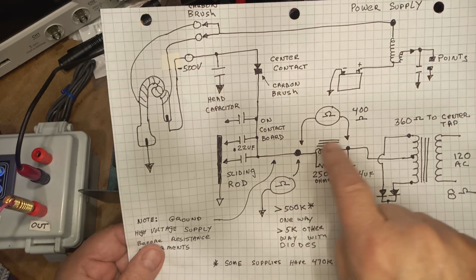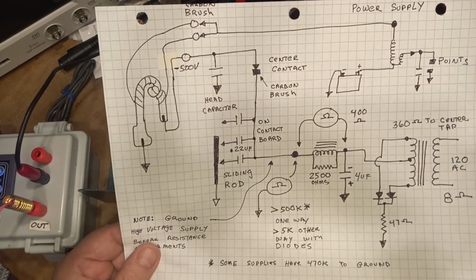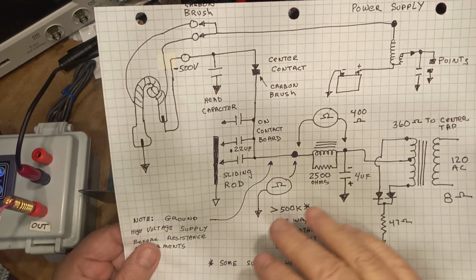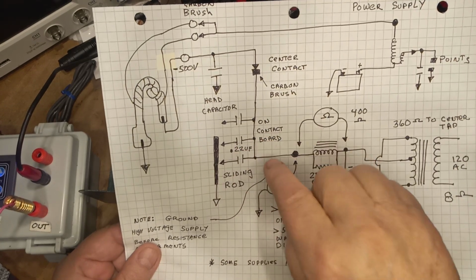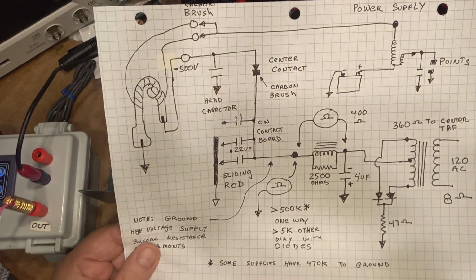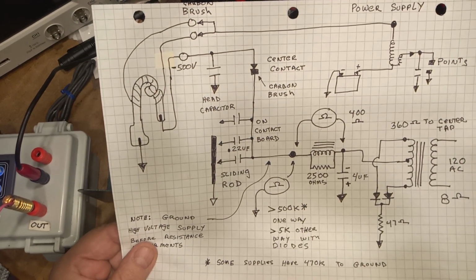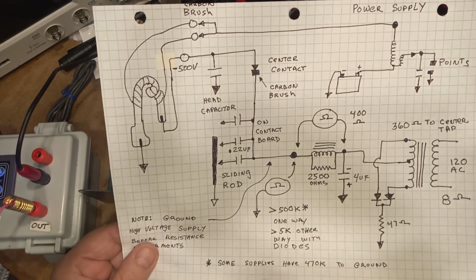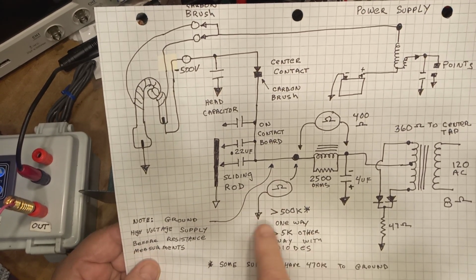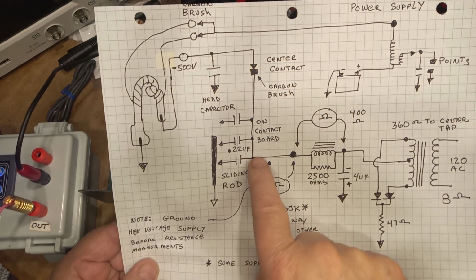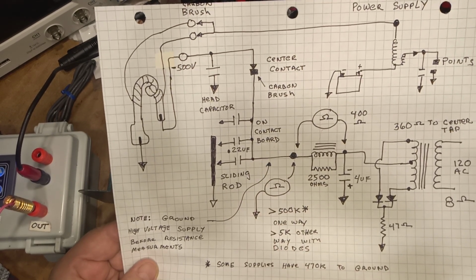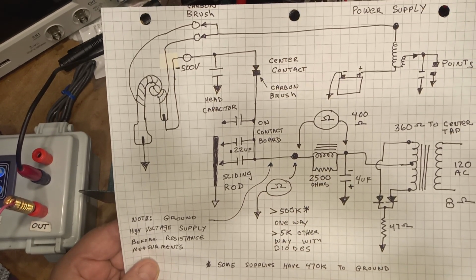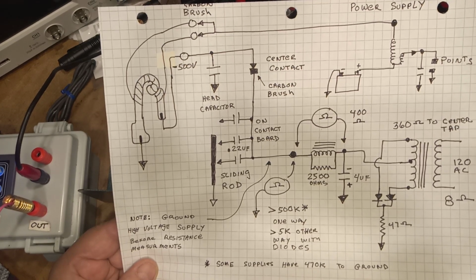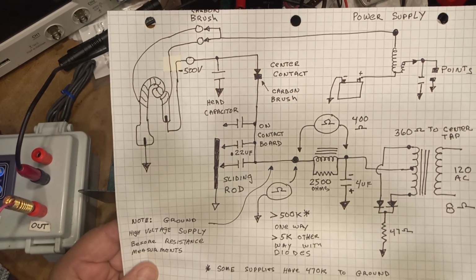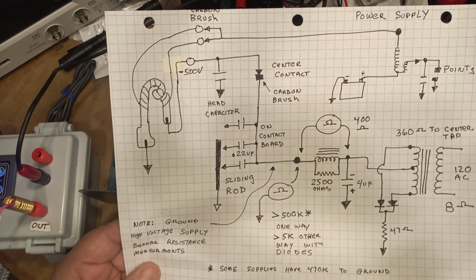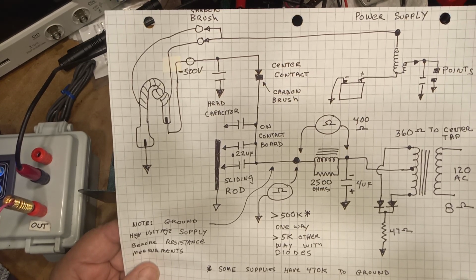So with your ohm meter, remember, power should be off, and you should have shorted out this high voltage to make sure there's no voltage left on the capacitors. Like I said, the later ones have a 470K resistor to ground that will drain it off over time. It takes at least 5 minutes to get the charge really down. You can't make your ohm meter measurements without the voltage being set to 0.